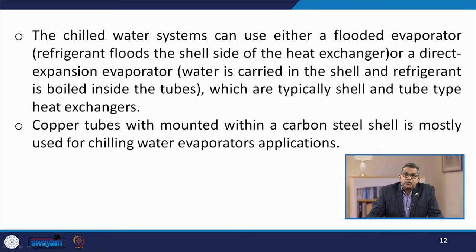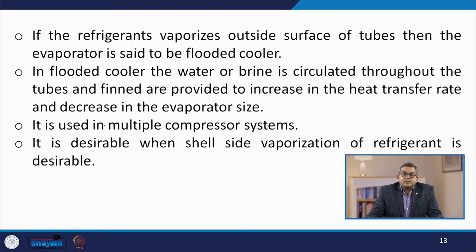Copper tubes are usually mounted within a carbon steel shell, mostly used for chilling water and evaporating applications. If the refrigerant vaporizes outside the surface of the tube, the evaporator is called a flooded type cooler. In a flooded cooler, water or brine is circulated throughout the tubes and fins are provided to increase the heat transfer rate and decrease the evaporator size; it is used in multiple compressor type systems. If they vaporize inside the tube, it is called a dry cooler, where refrigerant flows through the tubes and water or brine is circulated through the shell side.